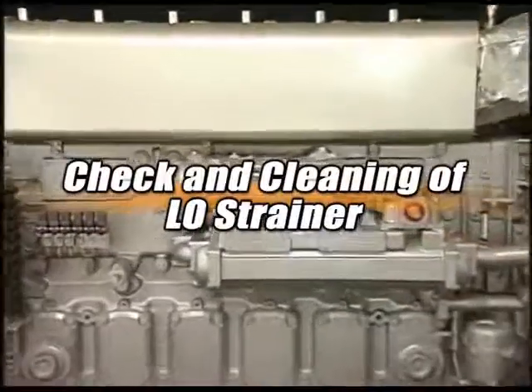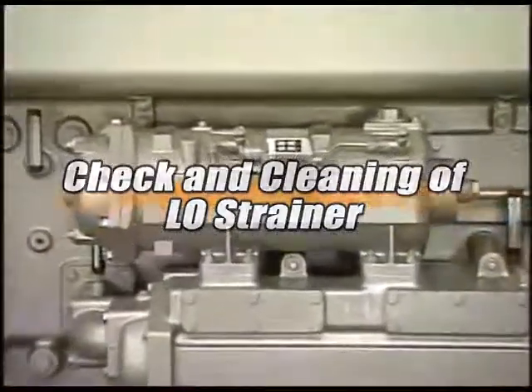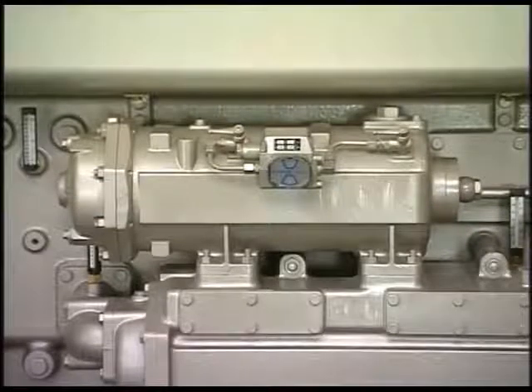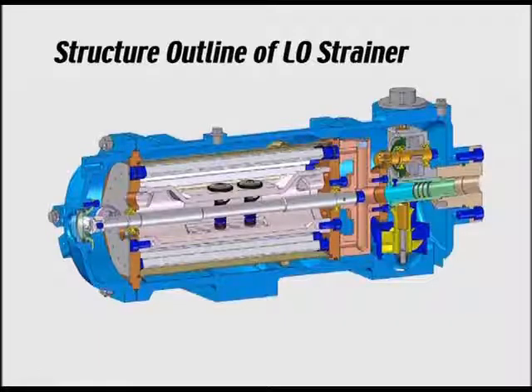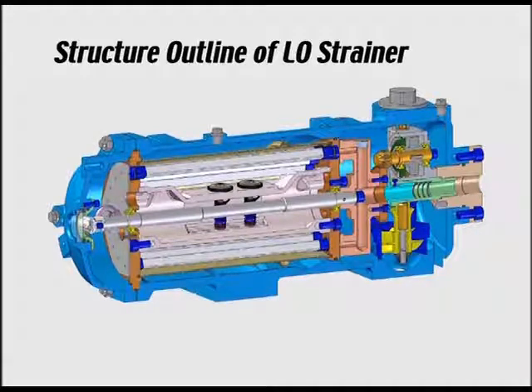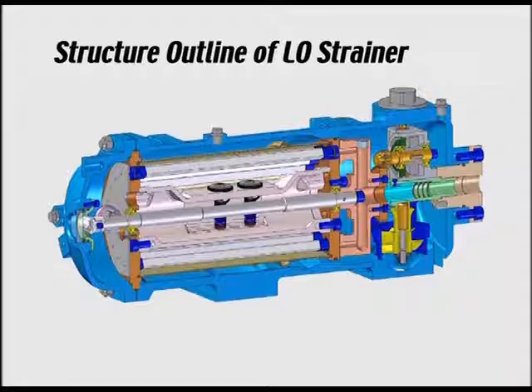The lube oil strainer fitted on this engine is an automatic backwashing filter. Lube oil is filtered by running from the inside to the outside of the strainer element. The cleaning nozzle rotates during operation, driven by a turbine powered by lube oil pressure. At the tip of the nozzle, the flow of lube oil is reversed, dirt is discharged, and filtration and cleaning are constantly repeated.